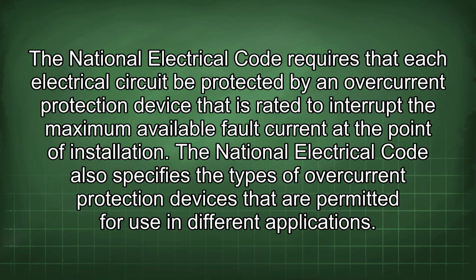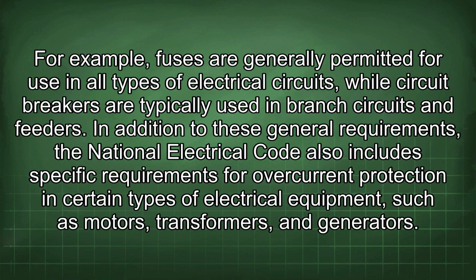The National Electrical Code requires that each electrical circuit be protected by an overcurrent protection device that is rated to interrupt the maximum available fault current at the point of installation. The National Electrical Code also specifies the types of overcurrent protection devices that are permitted for use in different applications. For example, fuses are generally permitted for use in all types of electrical circuits, while circuit breakers are typically used in branch circuits and feeders. In addition to these general requirements, the National Electrical Code also includes specific requirements for overcurrent protection in certain types of electrical equipment, such as motors, transformers, and generators.